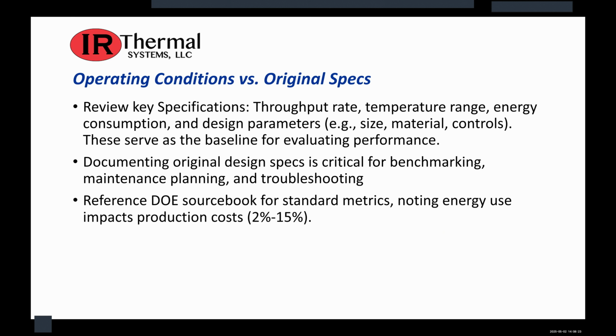It's important to review your key operating specifications and particularly the design specifications, understanding the throughput rate, temperature range, energy consumption, and design parameters that were originally defined with the equipment. These serve as the baseline for evaluating your current performance. You want to make sure you document the original design specs, and this is critical for benchmarking, maintenance planning, and troubleshooting. You can reference the DOE sourcebook for standard metrics, noting that energy use impacts production costs. Energy use is 2 to 15% of your production costs with large-scale dryers and heaters.